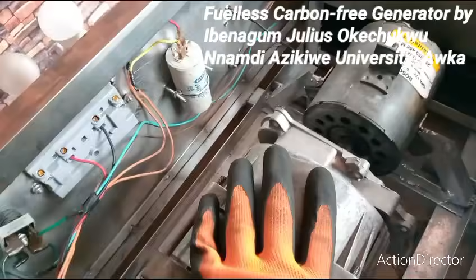The capacitor is connected to these orange wires. The function of the capacitor is to store energy, which energizes the current coming from here to give you the 220 or 230 volts required. If you disconnect this capacitor, you will not have enough voltage to power the load. This capacitor comes with a capacitance, and for this size of generator it is 24 microfarad.